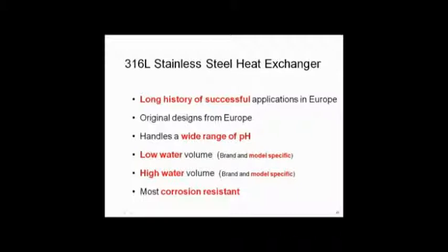But I caution you, you need to look at your brand of heat exchanger, the product you're buying, to see which way it may be. That's why I've got the double statement, low water volume, high water volume, because it's going to depend on the brand. It's going to depend on the type of material you're using. Most of the time, the stainless is going to be a very low volume. And last comment, it's the most corrosion-resistant material we have out there, highly successful. Most of it will be stainless.